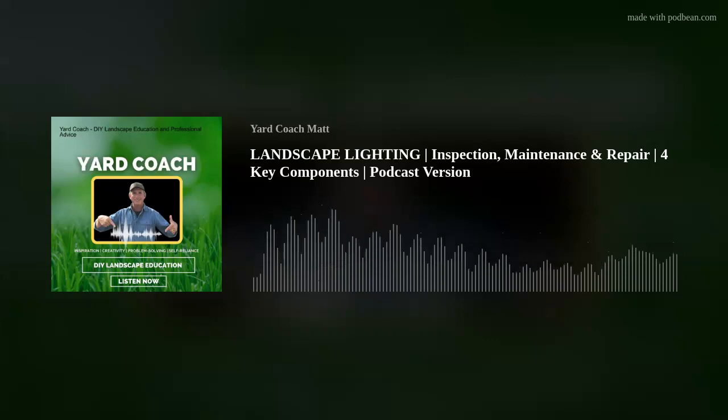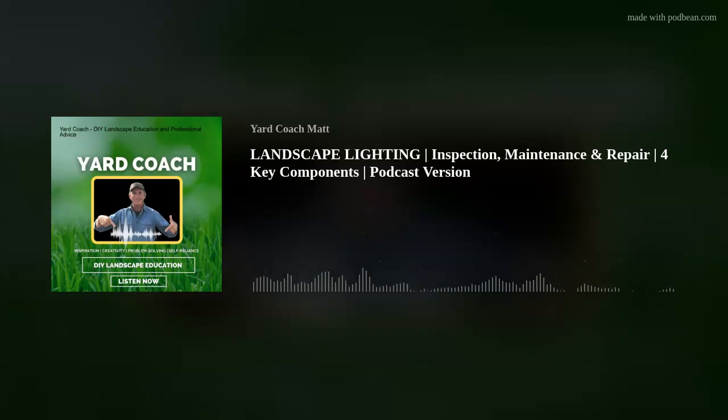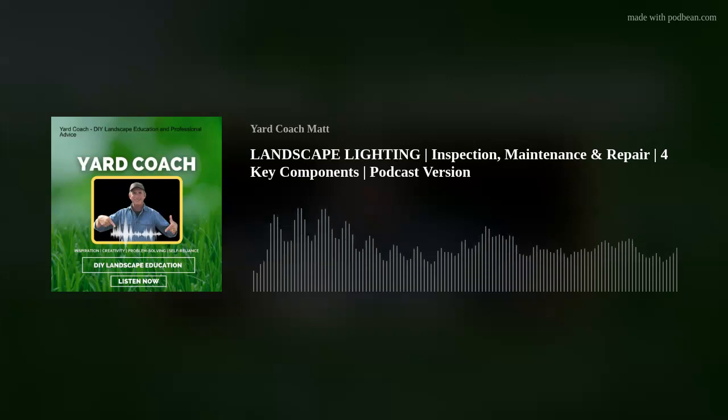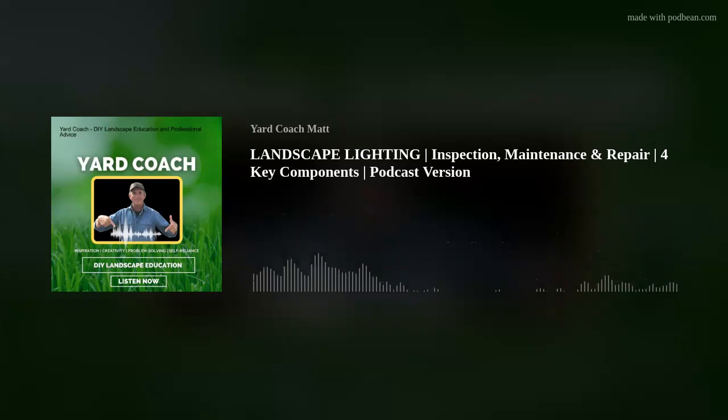It's a nice, easy way to know that the transformer is, one, working. Number two, it's actually doing its job as far as putting out the amount of voltage that it's saying it is. And you know that that wire, that cabling, is leaving the transformer with voltage in the cable. So it's one way to kind of knock out two birds with one stone.